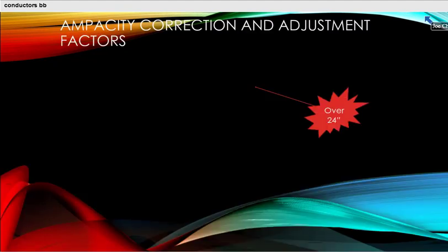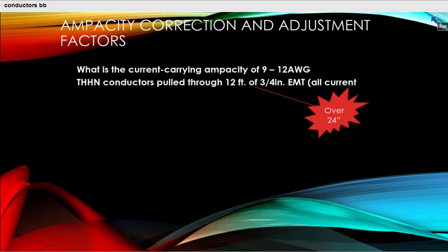So let's do an example. I left out this part. I meant to mention this just a minute ago. Whenever we look at a raceway, and this relief is given to us back in the notes to Chapter 9, whenever we do raceway fill, it'll tell us that if I have a raceway that's 24 inches or less, then I don't have to worry about how many conductors and discounting them or derating them because of that.